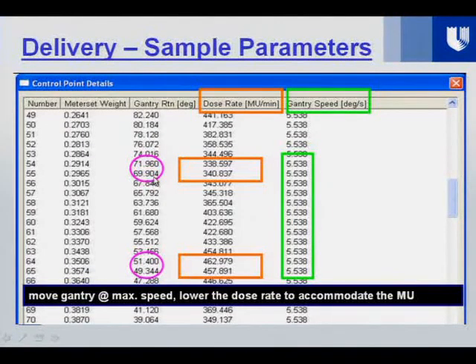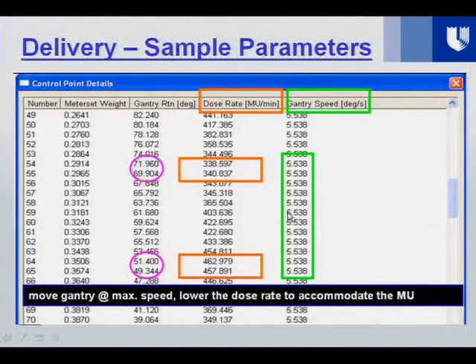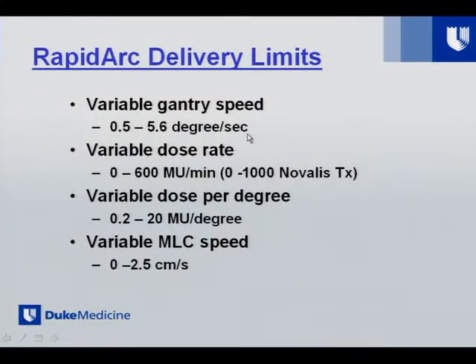One example shows the dose rate changing while the gantry speed is fixed; in another unit configuration, the gantry speed changes. For Novalis TX, the dose rate range is 0 to 1,000 MU/min; TrueBeam has even more. The variable dose per degree ranges from 0.2 to 20 MU per degree, and MLC speed ranges from 0 to 2.5 cm per second. We need to look at QA requirements for higher MUs and sensitivities with these varying parameters.